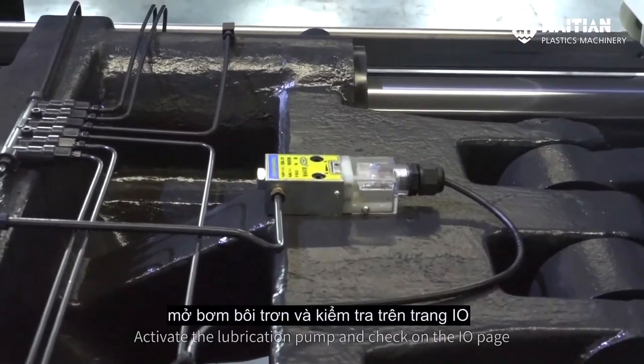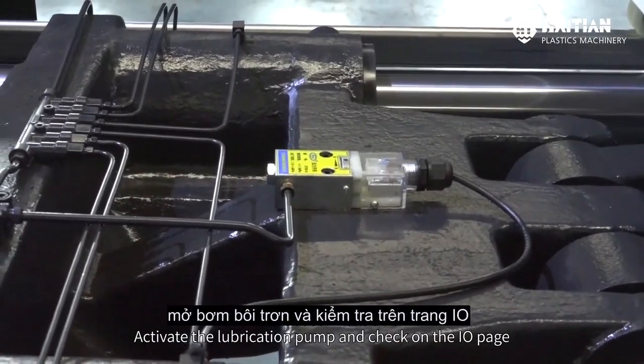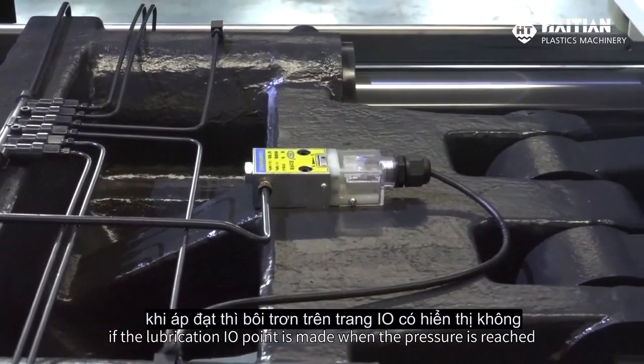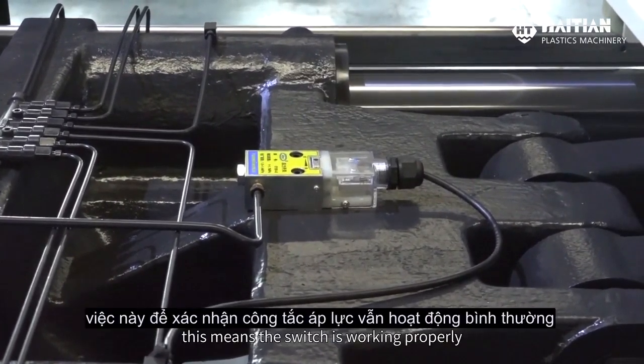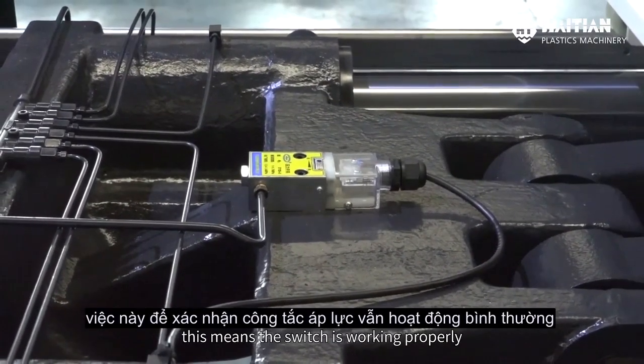Lubrication pressure switch. Activate the lubrication pump and check on the I/O page if the lubrication I/O point is made when the pressure is reached. This means the switch is working properly.